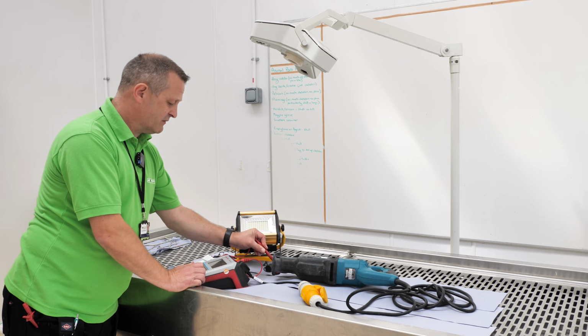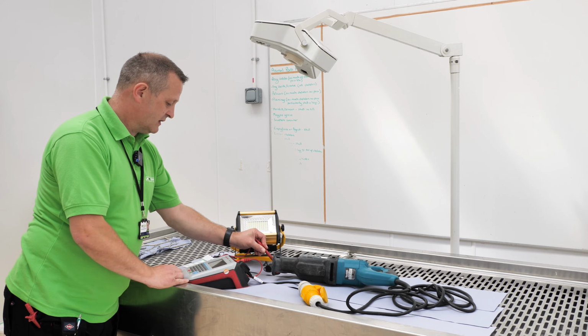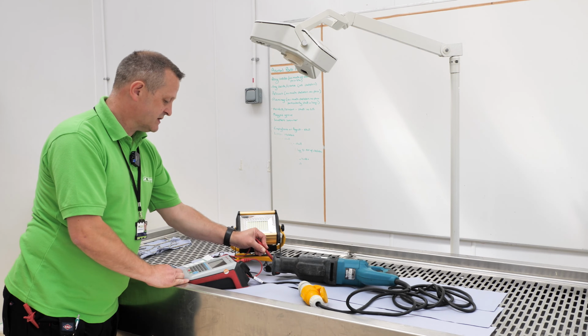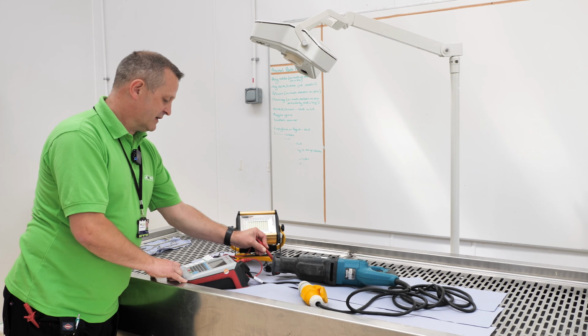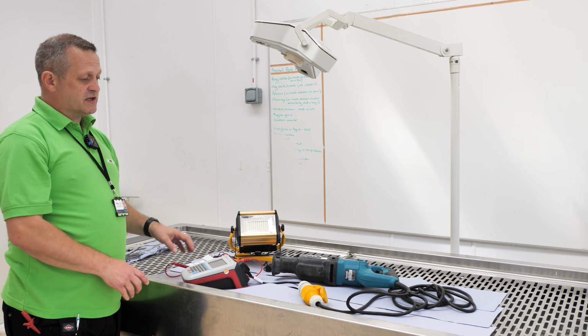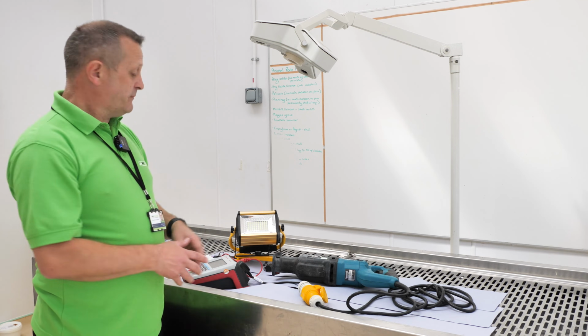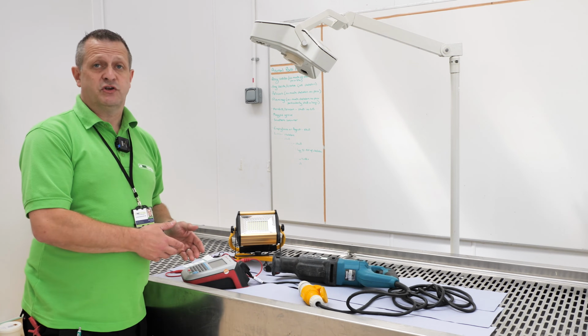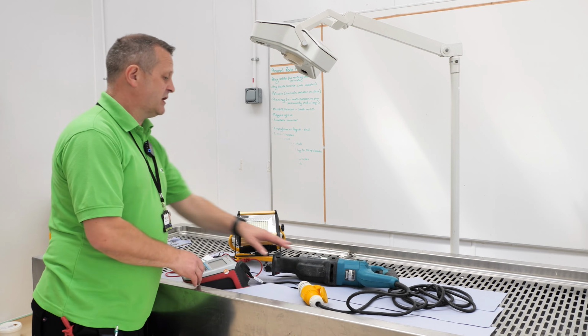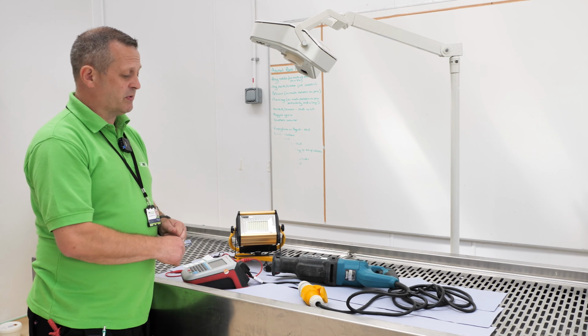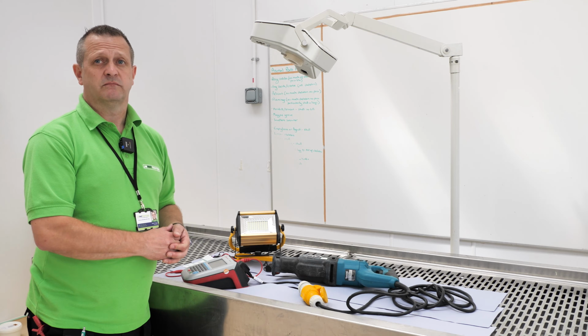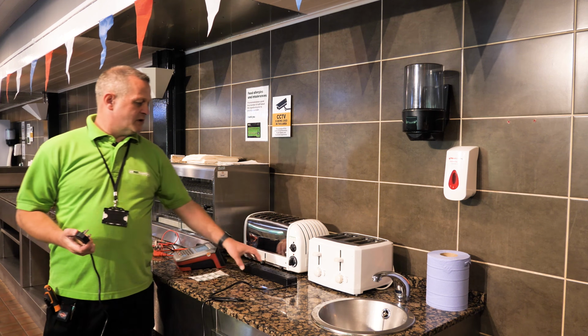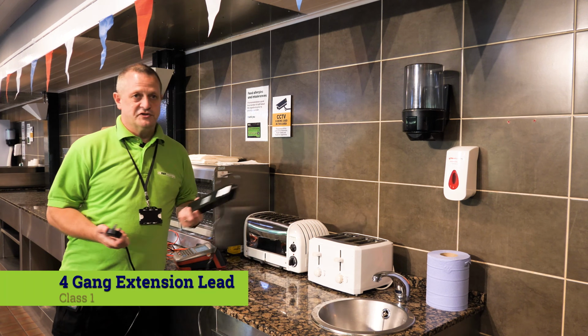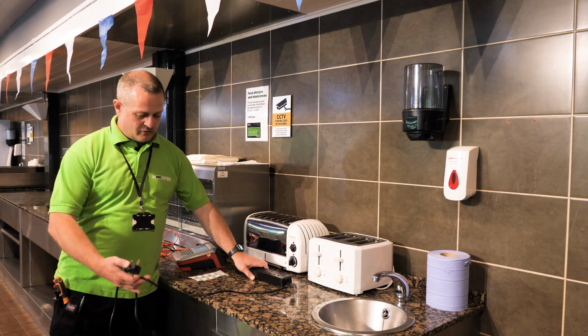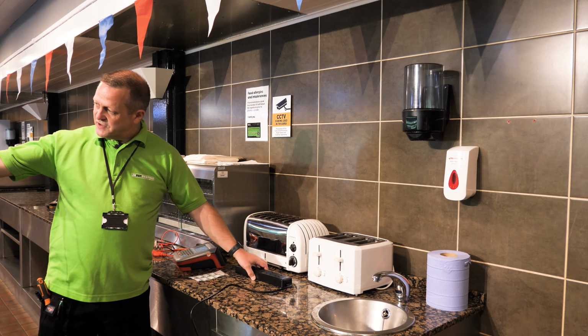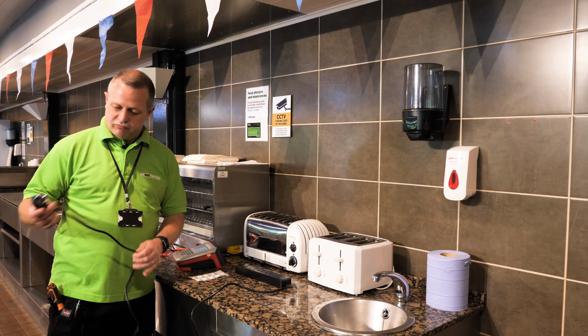Again, that's shown perfectly fine. Then it's doing a leakage touch current test. That's showing perfectly fine as well, and that's the test complete. Again, we just fill in the machine for those results, attach a label on a nice clean part of the appliance, and that's the test complete. Okay, so now we're going to look at testing a typical 4-gang extension lead. So probably about a 2 meter length of cable roughly.